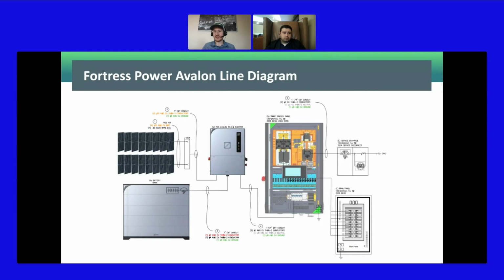I'd add quickly that this comes very close to plug and play for a residential system, because you have the inverter, the smart energy panel, and the battery. Your existing grid goes to the smart energy panel, and your existing main electrical panel connects to the load port of the smart energy panel. That means you don't have to add combiner boxes or additional load shedding, and you don't have to worry about breakers as much.